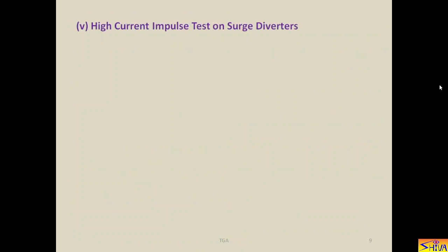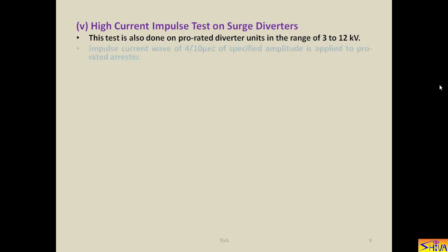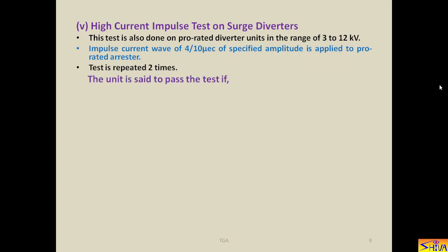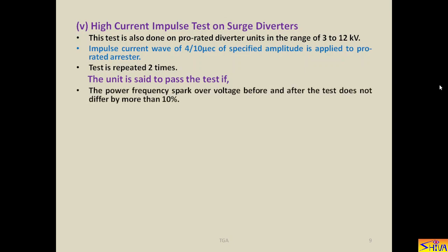Last is the high current impulse test on surge diverters. This test is also done on prorated diverter units in the range of 3 to 12 kV. An impulse current wave of 4 by 10 microsecond of specified amplitude is applied to the prorated arrestor. The test is repeated 2 times. The unit is said to pass the test if the power frequency spark-over voltage before and after the test does not differ by more than 10%. It means the unit is intact after performing this test.